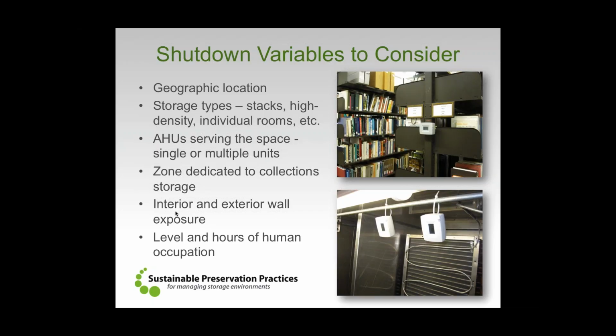We had to think about how much time the system could be turned off and how much fluctuation in the space was acceptable. Now, storage types, stacks, high-density individual rooms can play into this as well. The more material you have in the space, the more that material will act as something of a heat sink. And as you turn off the system, the thermal mass of the material that is stored in the space can actually run its own environment for limited periods of time. And that was actually shown to be true as part of our equilibration research also.